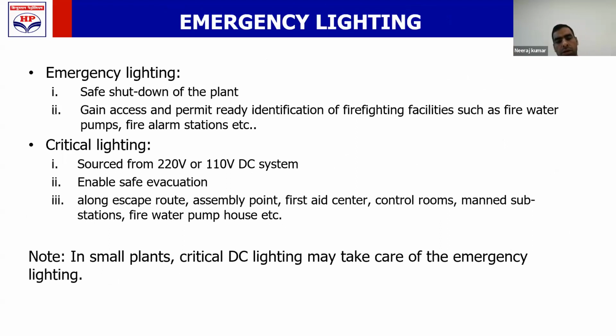Another critical requirement for fighting a fire and for escape of the person is emergency lighting. So emergency lighting shall be provided for the safe shutdown of the plant. You will need emergency lighting for what reason? So that you can safely shut down your plant in case of emergency, and to gain access to your firefighting equipment. So your emergency lighting should be designed thinking about which locations need light to access the firefighting equipment and to shut down the plant. Accordingly, emergency lights should be placed.